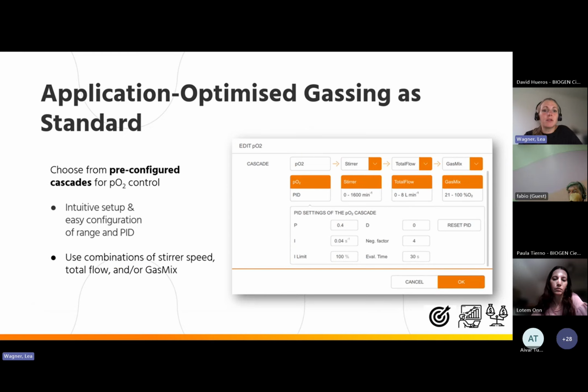Another cool feature of the touch controller is the application optimized gassing, which is standard. So the customer can choose from pre-configured cascades for PO2 control, also for pH control basically. But here you can see it for oxygen control.